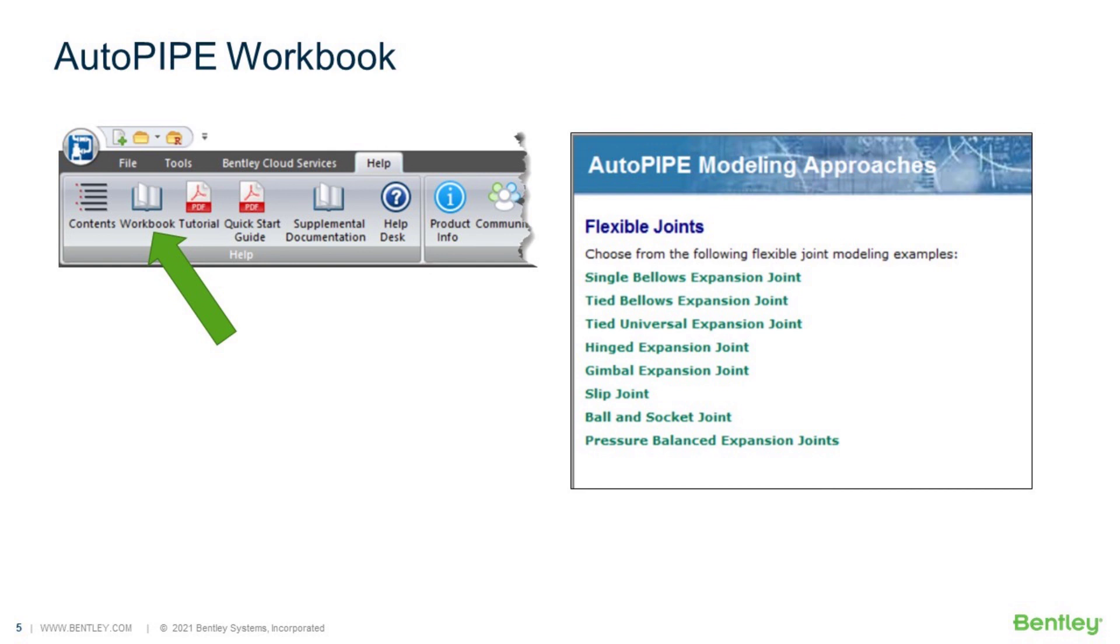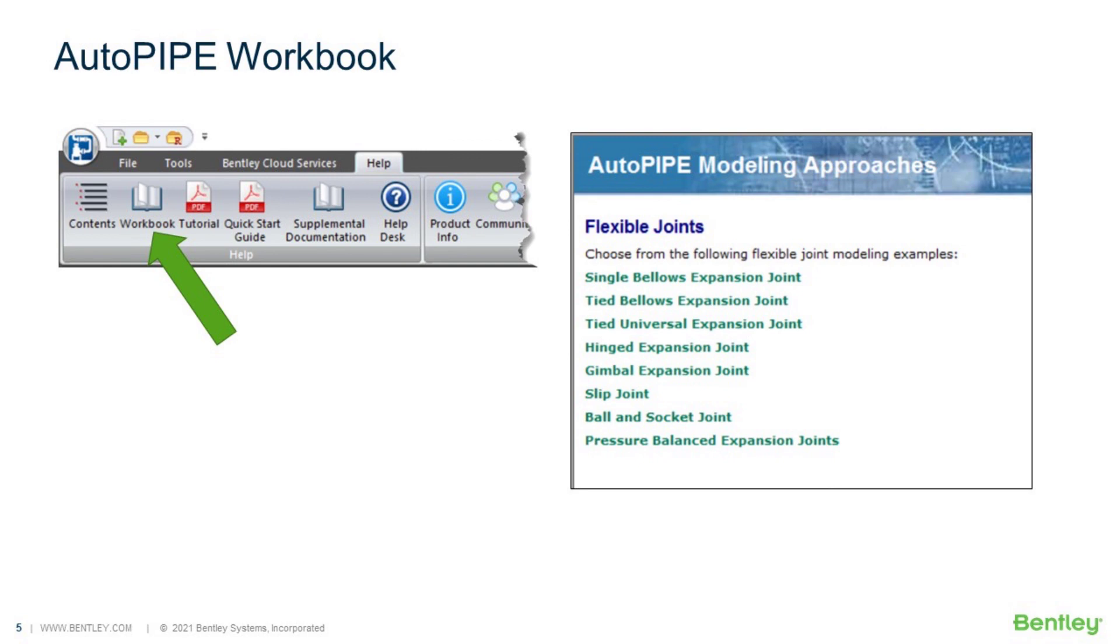All right, so let's go back and let's explore some different types of expansion joints. So we're going to take a look at single untied, single tied expansion joints, hinge expansion joints, gimbal expansion joints, slip joints, tied universal joints, ball and socket joints, and pressure balance joints. And if you're not aware, AutoPipe does have a workbook available that has recommended modeling approaches for different types of components. And one of these types of components is a flexible joint. So this shows on the right a list of the modeling approaches available that we kind of guide you through an example of modeling the flexible joint and which inputs should be changed versus which ones should not be changed and also some general guidelines. So we'll talk more about what it does guide you to do and what you are responsible for doing in inputting a flexible joint.